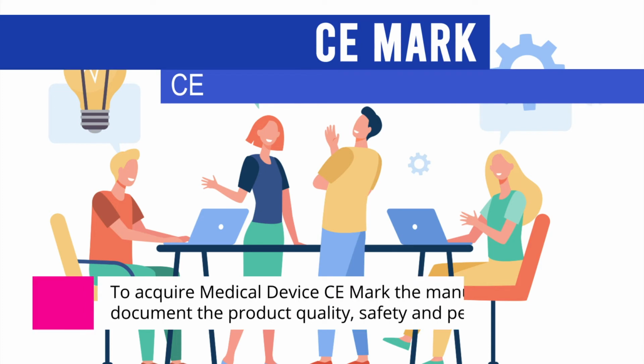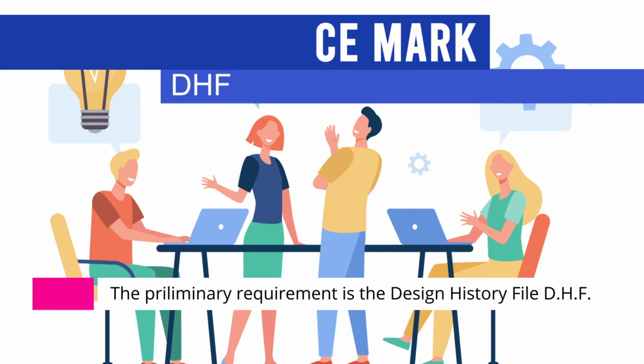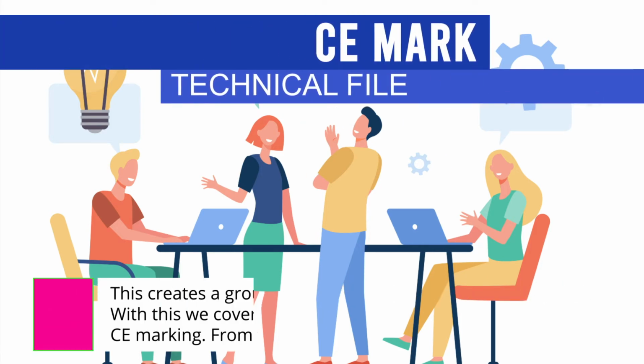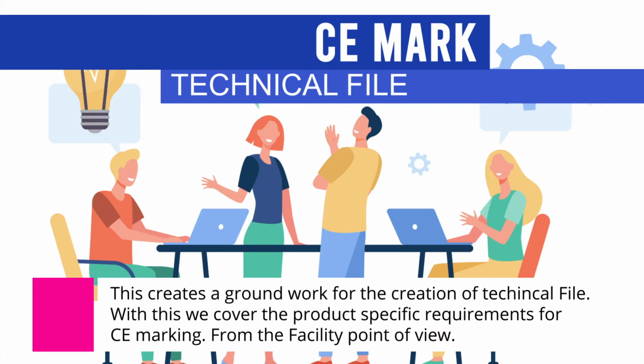CE mark. To acquire medical device CE mark, the manufacturer must document the product quality, safety, and performance. DHF. The preliminary requirement is the design history file, DHF. Technical file. This creates a groundwork for the creation of technical file. With this we cover the product-specific requirements for CE marking.